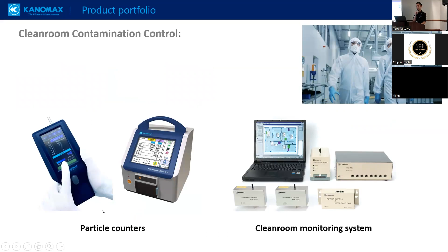Next is the clean room contamination control segment. I introduced a particle counter for indoor air quality, but many clean room contamination testing professionals use a handheld or portable particle counter to test and classify clean room levels. We also offer a monitoring system so clean room users can monitor and check the cleanliness data of their facility and track incidents. If a contamination event happens, they can review the data and fix the problem afterward.